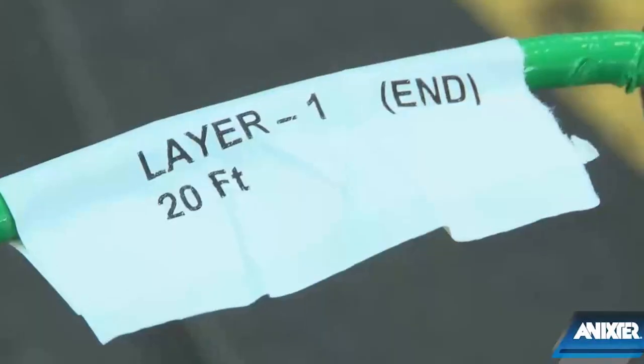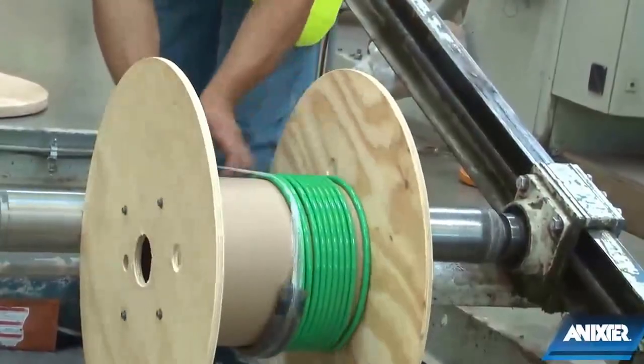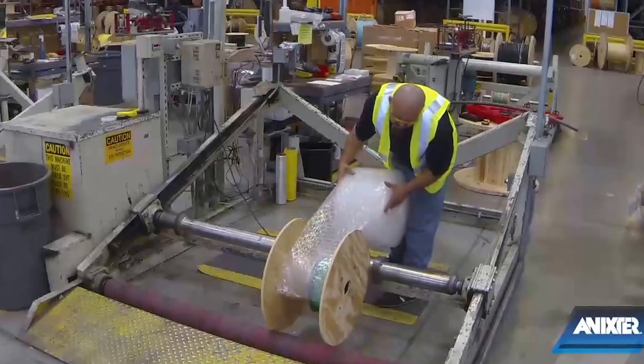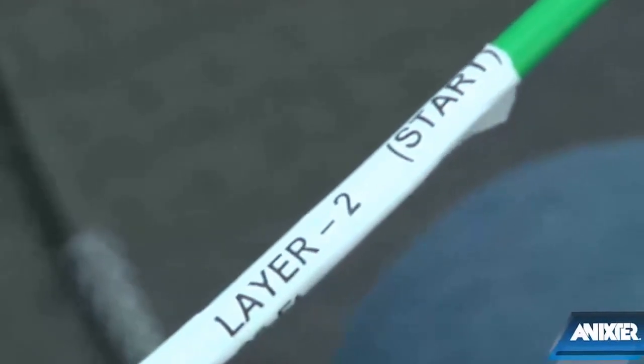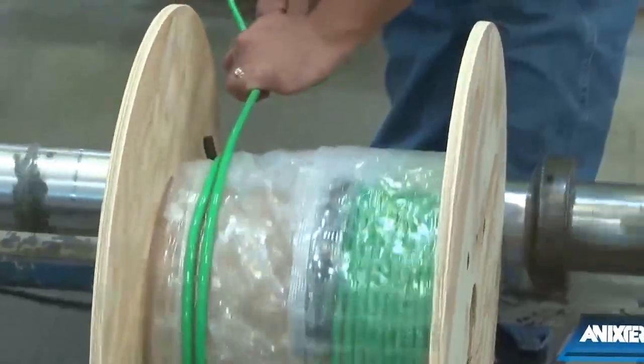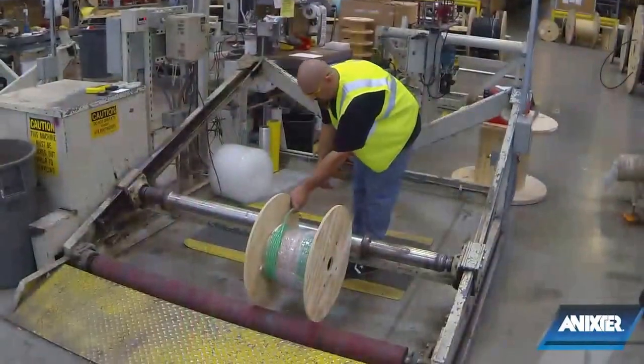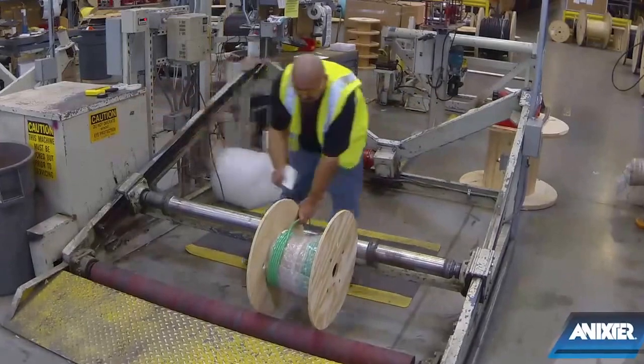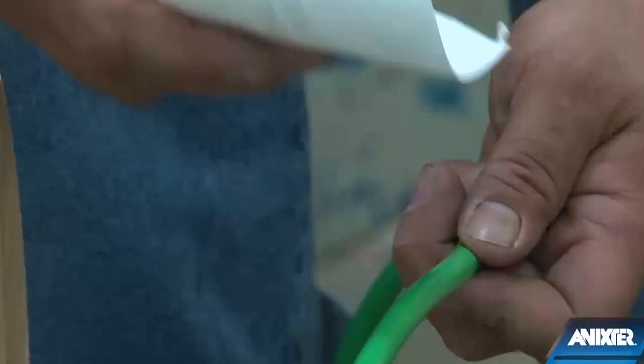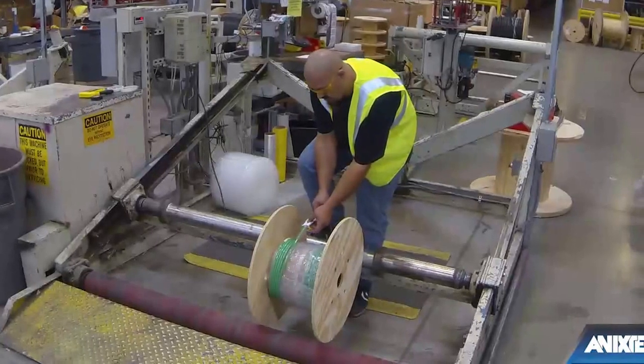When you know your pull sequence, or when you have the flexibility to pull whichever circuit you want first, Anixter can layer multiple circuits onto the same reel by putting the first circuit length on, attaching a pulling eye if required, and then applying another circuit over the top of it. This can be repeated multiple times until the sum of all circuit lengths reaches the maximum fill rate of the reel. Each reel is delivered with the lengths and circuit identifications clearly marked on the reel tags.